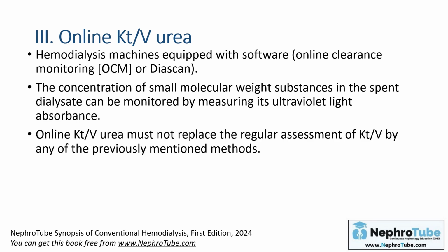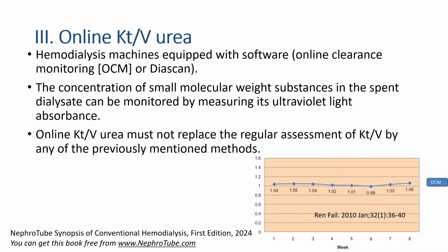But it is important to know that online KT/V urea must not replace the regular assessment of the delivered KT/V by the methods we mentioned before, such as single pool, equilibrated, or standard KT/V. Why? This is a study I didn't mention in my book. They took the OCM, the online KT/V, of a patient through 8 weeks.